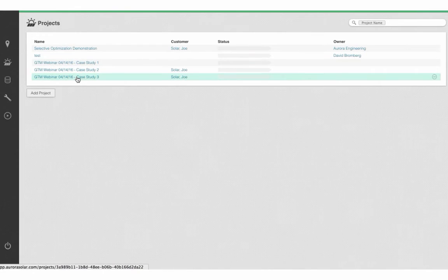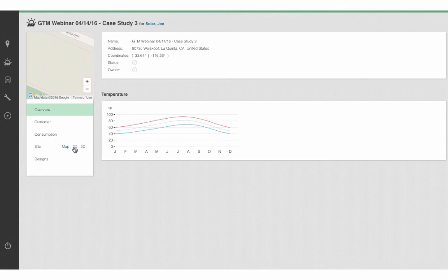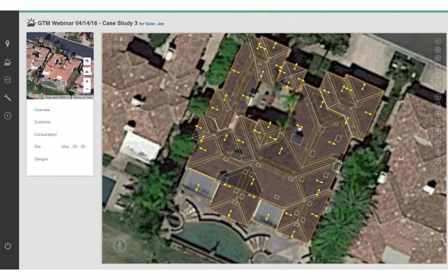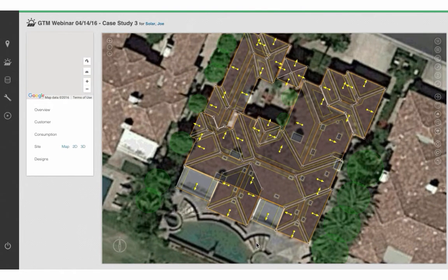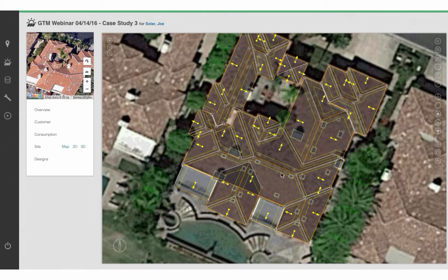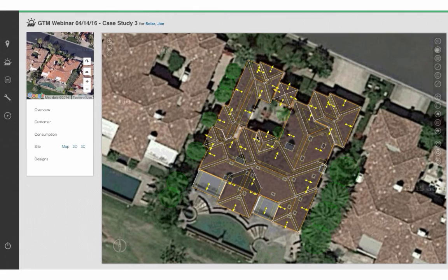Let's go ahead and look at an example which combines both scenarios. This site is especially complex — we have a nice big house, but unfortunately we don't have one nice contiguous roof area on which to place all the modules. One roof looks like it has some potential, but unfortunately there are trees on the right side which will probably lead to a lot of shading. We also have a chimney which will cause shading in its surroundings, and generally many of these roofs are broken up in different orientations, so it's likely we will have to span the entire roof to offset the energy consumption of a house of this nature.